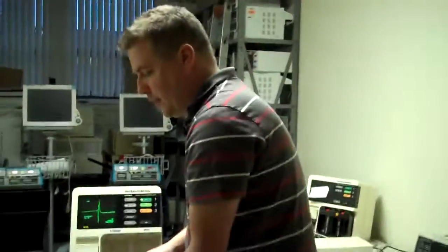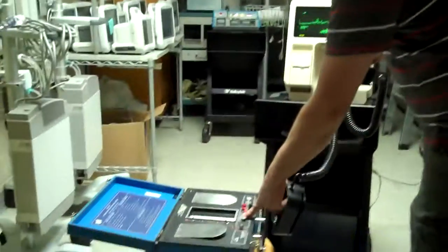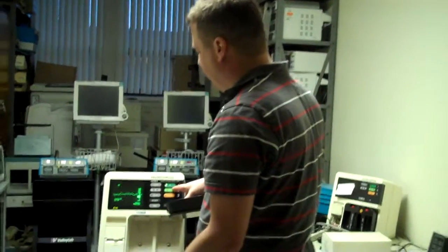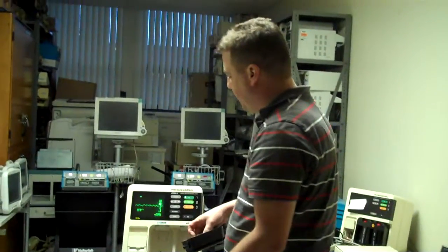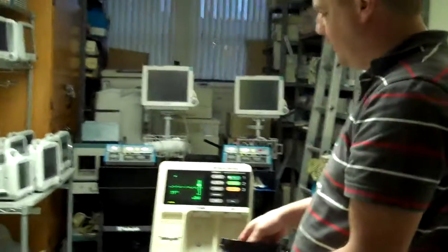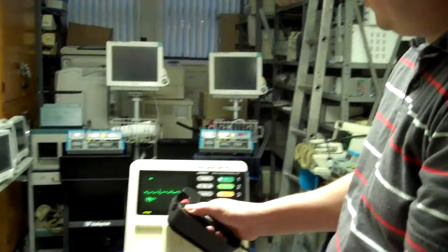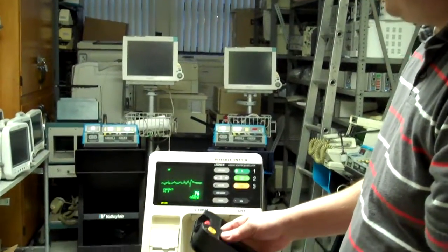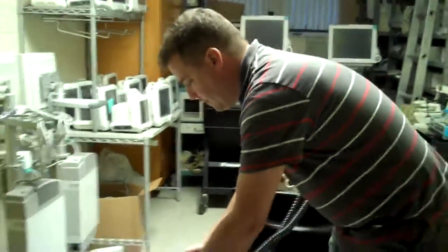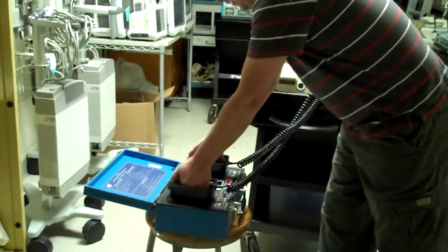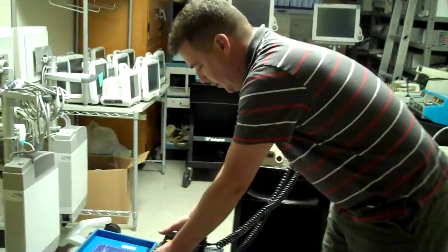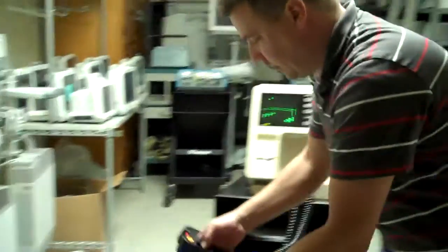So then I'll change my range up to 500, and I will select an energy reading of about, we'll go for 100, that's right in the middle of our available ranges. Then I'll recharge. And now we're ready to check that as well. And we're right at 100 joules, and that looks great.